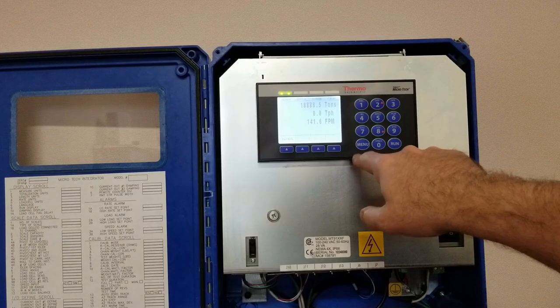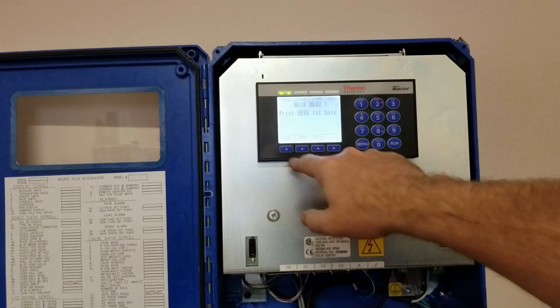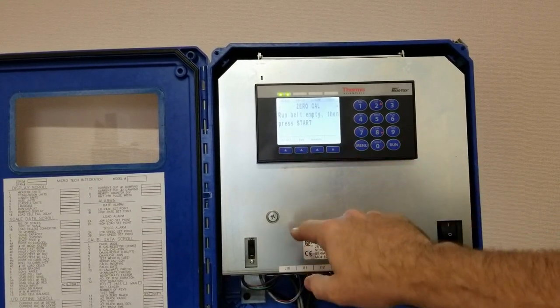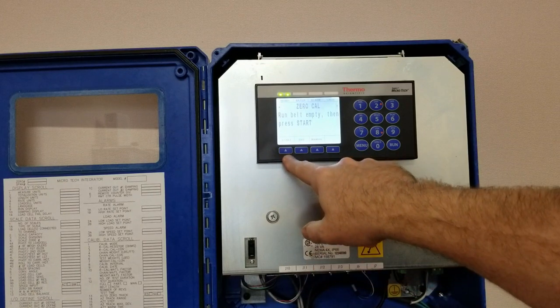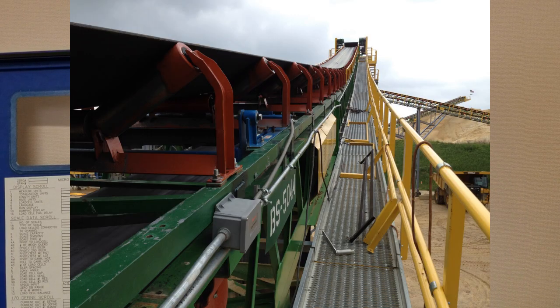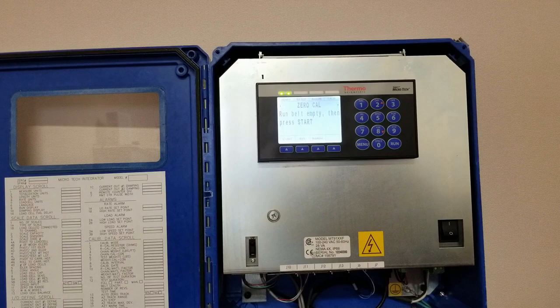What you want to do is press menu and then press zero cal, and then you want to run the belt empty. Normally you want to run the belt empty for at least 10 minutes. Typically, if this is done in the morning, you want to limber up the belt a little bit, so you want to run it for at least that length of time.